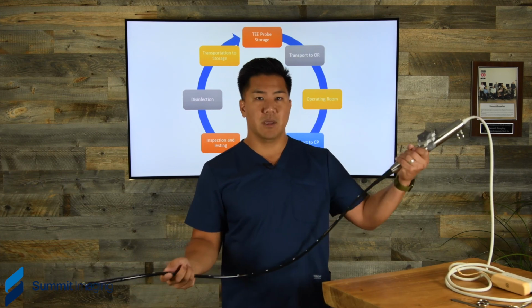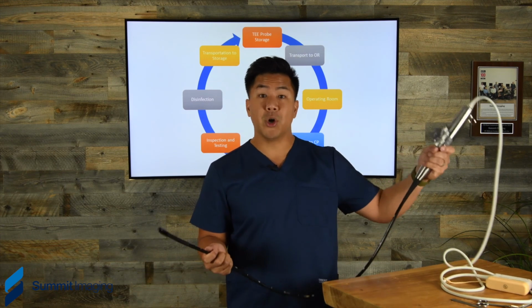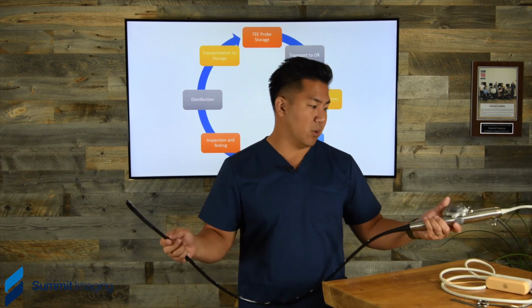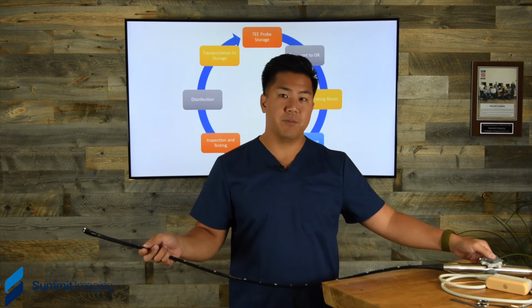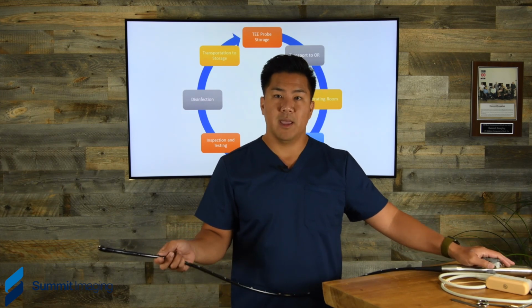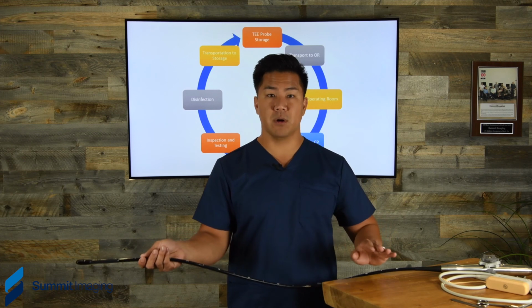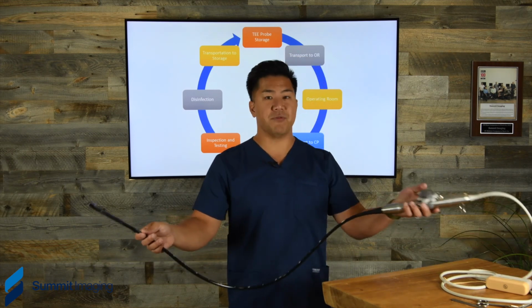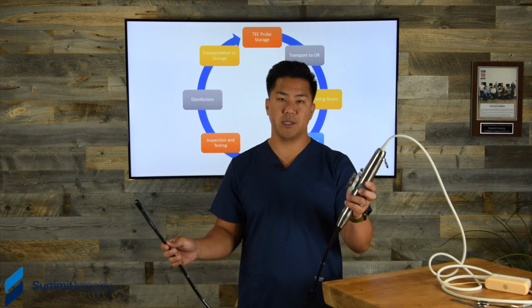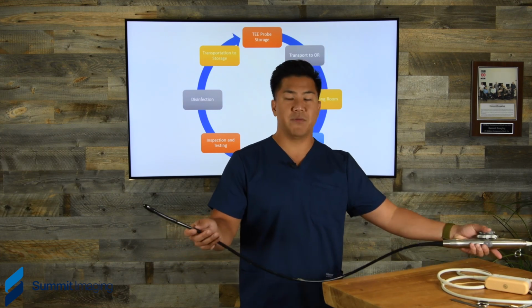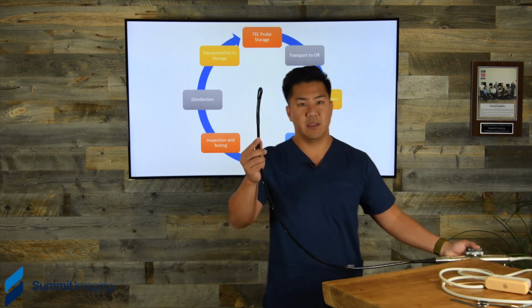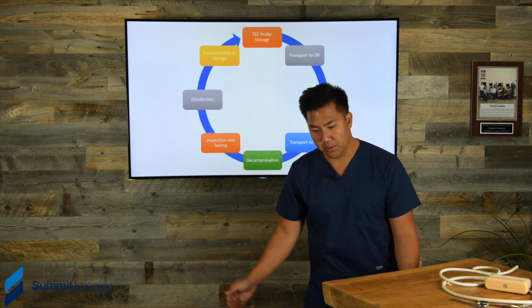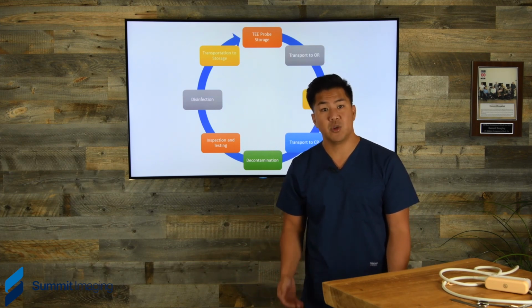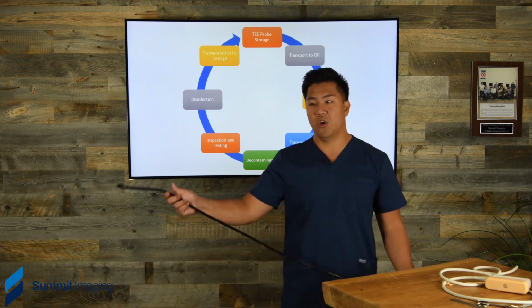We recommend that it's stored hooked next to a patient, but we often see that this probe is resting somewhere, and once the procedure's over, this handle is very heavy. This is the heaviest part of the transducer. It will slide off of a surface and then drag this probe down, and the probe will smack and hit that. So if you heard that smack, that probe is now broken.